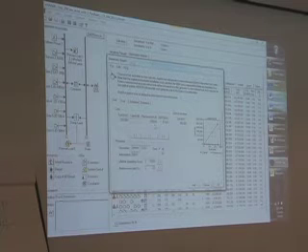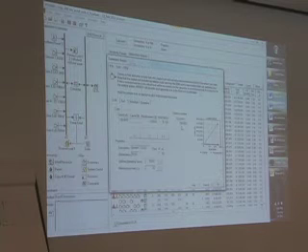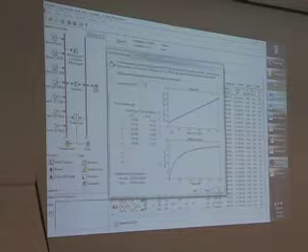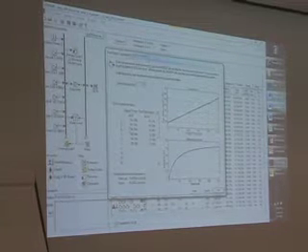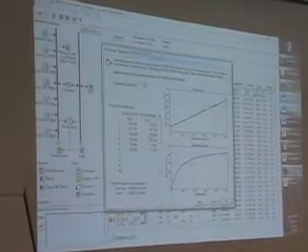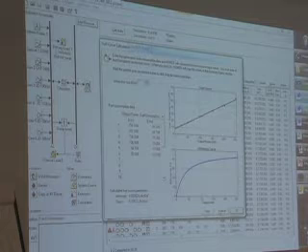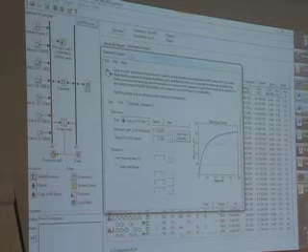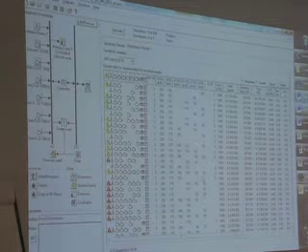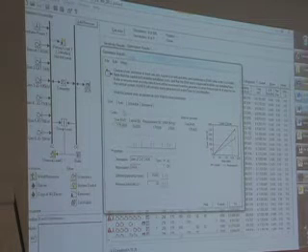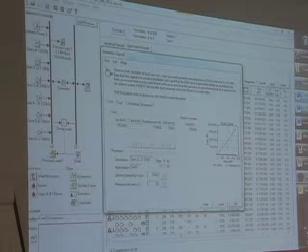And the replacement, so what we're saying is after 15,000 hours, we're going to need to spend $256,000 to replace this 256 kilowatt generator. And did we use the fuel curve calculator? So we calculated the fuel curve by entering in here the full load fuel consumption and the part load fuel consumption. So that one's existing, and you said this one's existing also, right? So we should do that.